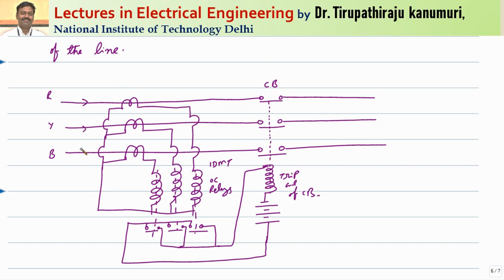Whenever current passes through the primary, the secondary current is induced in the secondary side. That secondary current passes through your relay and returns back through the circuit. This overcurrent relay is set to operate depending on how much percentage of overload you want to allow. We set the plug setting multiplier and the time setting multiplier accordingly, depending on the value of overcurrent at which it should operate.